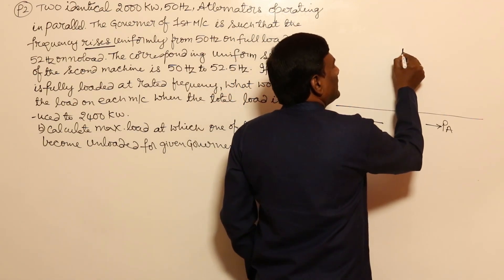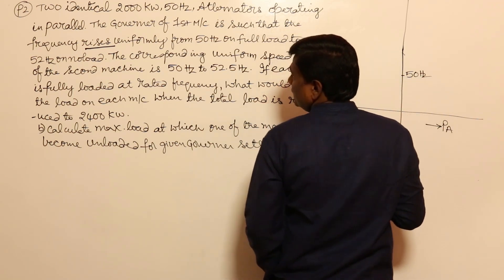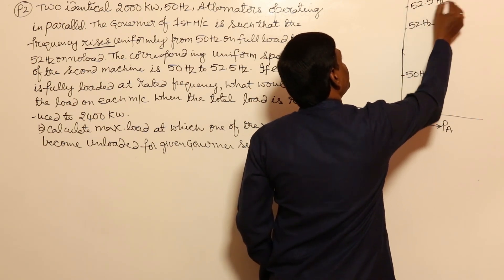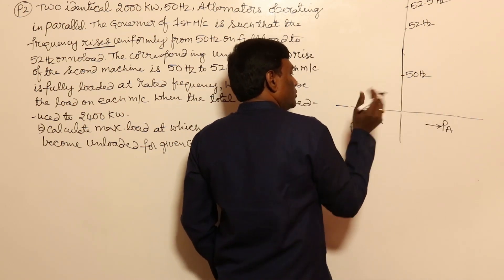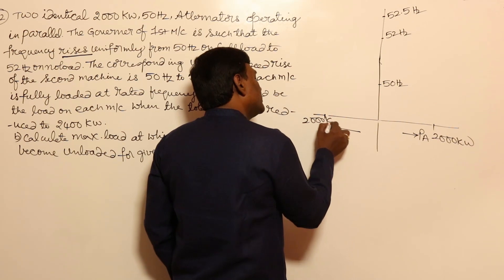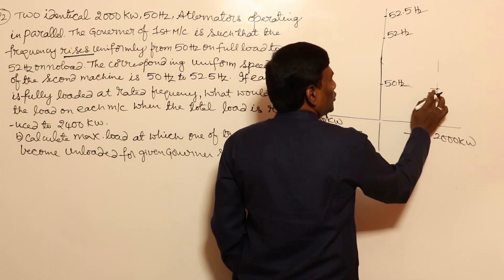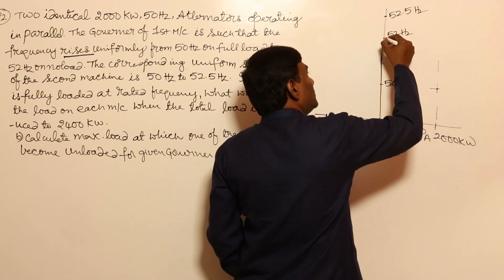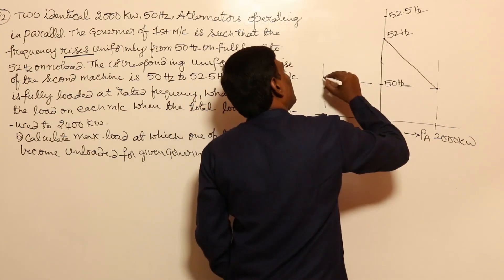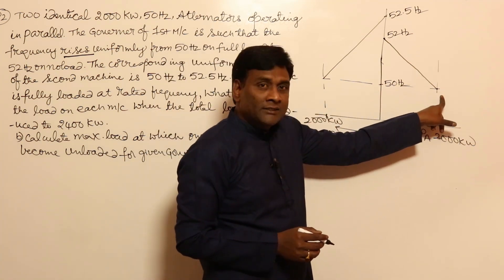So for the first machine, the frequency goes from 50 Hz to 52 Hz, and for the second machine from 50 Hz to 52.5 Hz. In both cases the rated capacity is 2000 kilowatt. At full load both machines operate at 50 Hz. As output power is reduced, frequency rises — to 52 Hz for the first machine and to 52.5 Hz for the second machine.